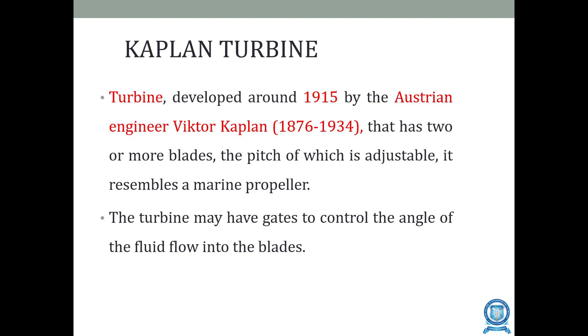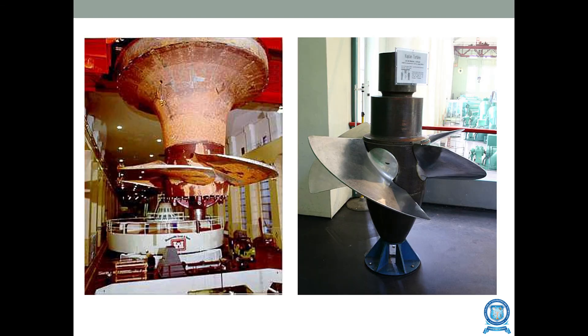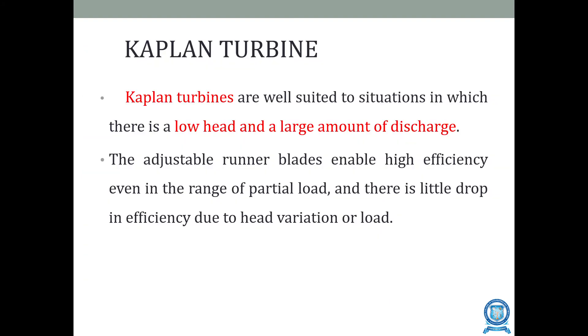The Kaplan turbine was developed around 1915 by Austrian engineer Victor Kaplan. It has two or more blades with adjustable pitch, resembling a marine propeller. The turbine can also have gates to control the angle of fluid flow into the blades. The Kaplan turbine is used where there is low head and a large discharge — opposite to the Pelton wheel. The adjustable runner blades give high efficiency even under partial load, with little drop in efficiency due to head or load variation.